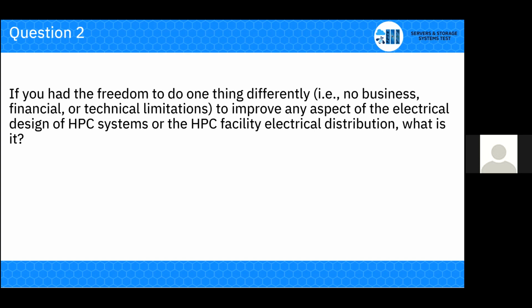Yes, good, thank you Christian. Load balancing - I believe most HPC facilities will use 3-phase power, whether Delta or Y. You're right about balancing, not only for the utility but also for those using UPSs, so you don't overload an inverter in a line. Exactly. Okay, good, thank you.